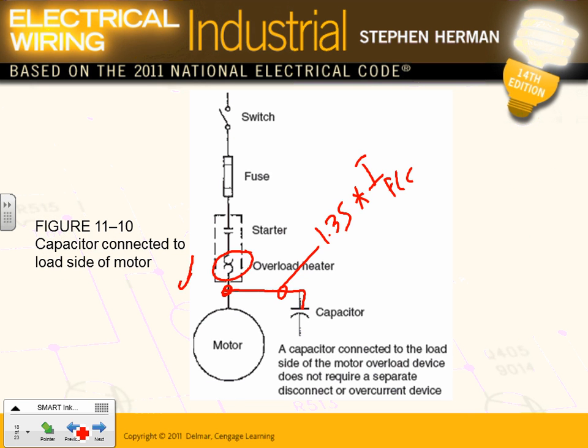This way is better, guys, because in this case, if this air handling unit is running, the capacitor will be on. If the air handling unit is off, what's happened to the capacitor? The capacitor is off. Any comments, guys? Any questions about that? Two ways of connecting your power factor.